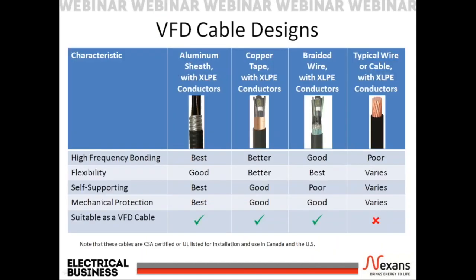The selection of a VFD cable may come down to the details of the installation as well as the characteristics of the cable. Note that typical wire and cable, such as RW90 and conduit or Teck 90 cables, should not be used for VFD applications. When it comes to the electrical performance of the cable, high frequency bonding in particular, the best overall cable design is the aluminum sheathed product. For an installation that demands repetitive movement of the cable, the best overall would be the braided wire construction. In these applications requiring flexibility, do not use the aluminum sheathed cable.